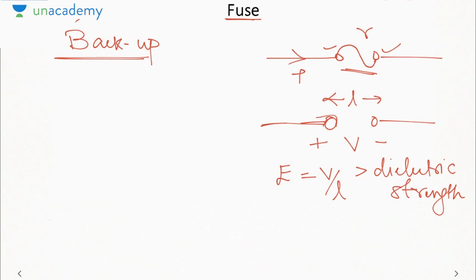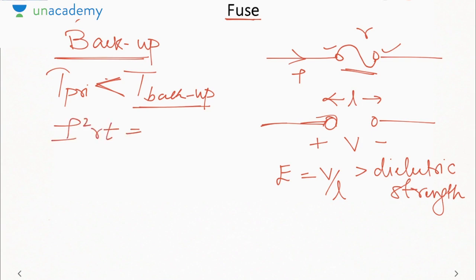Now obviously primary protection operates first, so T backup must be greater than T primary, where T represents the operating time. That is the time that it takes to open the circuit. If T primary is less than T backup, the primary must operate first. Since the operating time of your backup protection must be high, and we know how to decide operating time: I square RT is equal to the thermal limit. That means operating time is directly proportional to the thermal limit. So the thermal limit of the fuse must be high so that the operating time is high and it can be used as a backup protection.